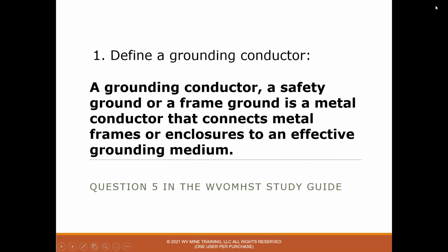So question number 1, define a grounding conductor. And the answer is a grounding conductor, a safety ground or a frame ground, is a metal conductor that connects metal frames or enclosures to an effective grounding medium. So all of our equipment has to be grounded to a very good ground. So if the equipment will become energized, if there would be an electrical phase of electricity gets against the frame, if you would walk up and touch that, you could get electrocuted.